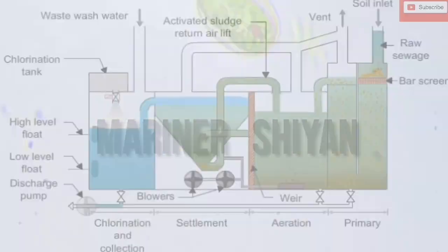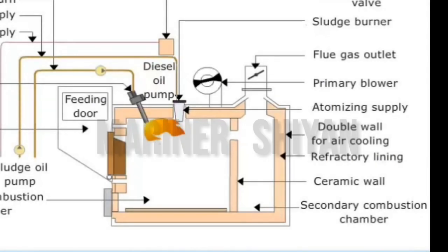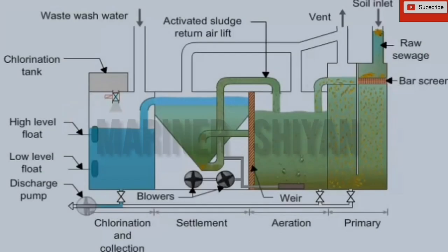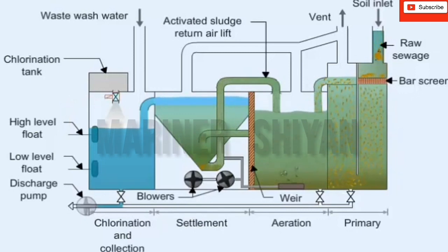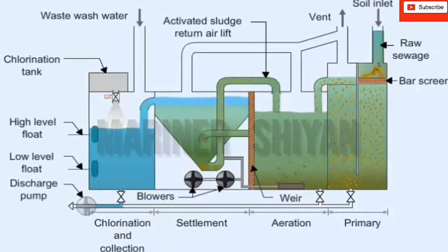Regular removal of sludge will prevent impairment of operation. The sludge is pumped overboard when the vessel is at sea, clear of areas where restrictions are in force. Small quantities can be burned in an incinerator, which is fitted in some vessels. Effluent discharged overboard through the sewage plant when the vessel is in port or restricted waters will have to meet certain standards. Tests have been established: one is a check of the quantity of solid material in the effluent; two others involve incubation of samples.